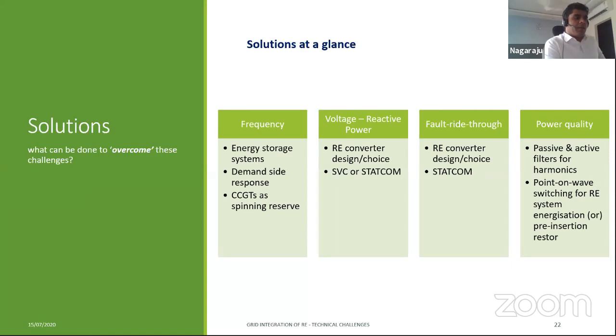So we are already there where the grids are seeing bottlenecks because of renewable energy sources. Then voltage and reactive power. The reactive power solution is again the converter design. Technically, there is no challenge, to be honest. The converters can be designed to provide as much reactive power as the grid wants. But everything comes with a price. Converters are expensive as the size increases. As the capacity increases, they become much more expensive because the IGBTs have limited capabilities because of thermal issues. So when you go to high voltage and high power levels, they become much more expensive than small rated IGBTs. It's not a proportional relation. It's almost an exponential relation.